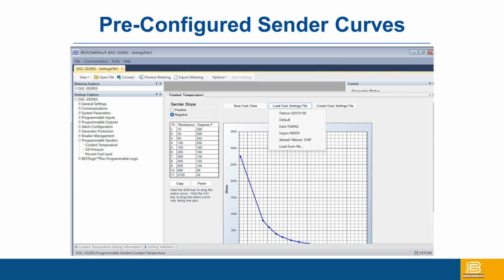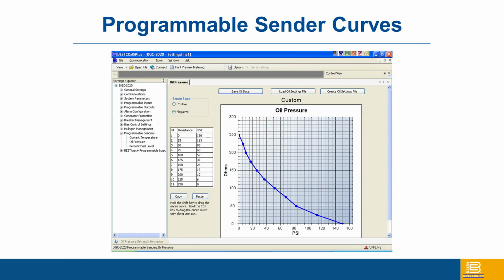Also loaded inside the software is pre-configured sensor curves, and there is a selectable option so that you know that you're using like a VDO sensor. A lot of the times we have those already pre-programmed, and you can just select it and download it. We also have programmable sender curves. So if the sender curve that you're using is not in our pre-configured selection, you can actually build your own sender curve through a table built into the BestComms.